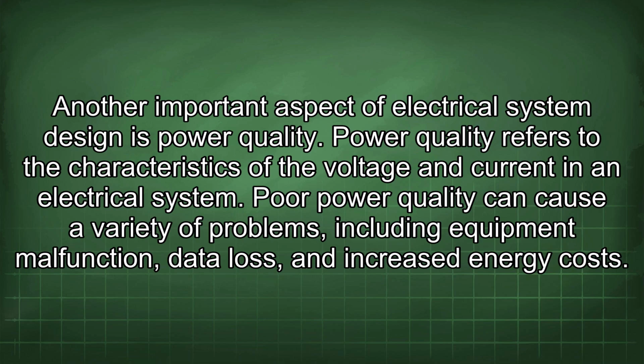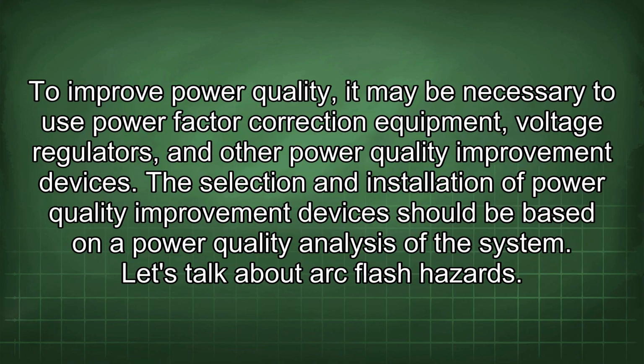Another important aspect of electrical system design is power quality. Power quality refers to the characteristics of the voltage and current in an electrical system. Poor power quality can cause a variety of problems, including equipment malfunction, data loss, and increased energy costs. To improve power quality, it may be necessary to use power factor correction equipment, voltage regulators, and other power quality improvement devices. Selection and installation of power quality improvement devices should be based on a power quality analysis of the system. Let's talk about arc flash hazards.